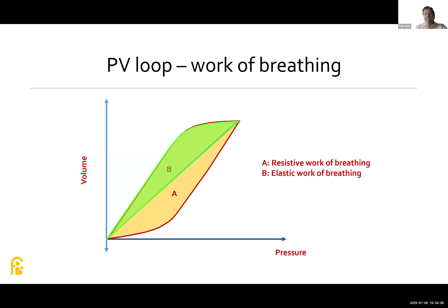We should also look at another aspect in the PV loop, the inflection point. You have two inflection points. One is the lower and the second one is the upper inflection point. The lower inflection point will guide us to optimize the PEEP. If the lower inflection point is too far from the zero or from the beginning of the pressure volume loop, that means we are not giving adequate PEEP. If it is near the origin of this loop, that means you are giving a good PEEP.